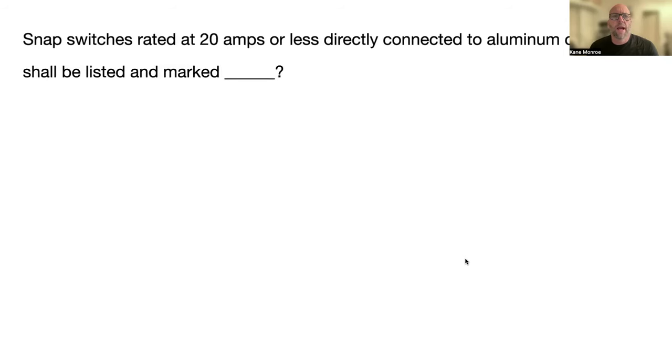Snap switches rated at 20 amps or less directly connected to aluminum conductors shall be listed and marked CO/ALR. So what that's telling is it's rated for copper and aluminum. That's on 404.14C.